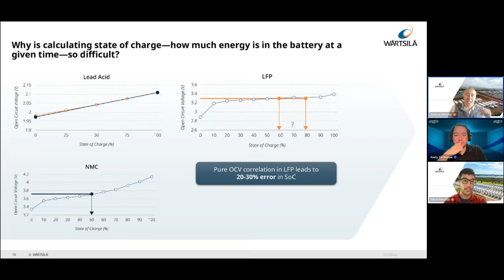There are three primary ways that we better our SoC estimate. The first is to calibrate on parts of the open circuit voltage curve where we do see some slope, where the open circuit voltage does mean something about the state of charge. Those are in the high and low SoC ranges, so in the 98, 99% state of charge on the high end, or on the low end at under 20 to 30% state of charge. We find that most batteries, including our BESS, work a little easier using the low end of that state of charge calibration range, because it's a little easier to steer into that wider range.